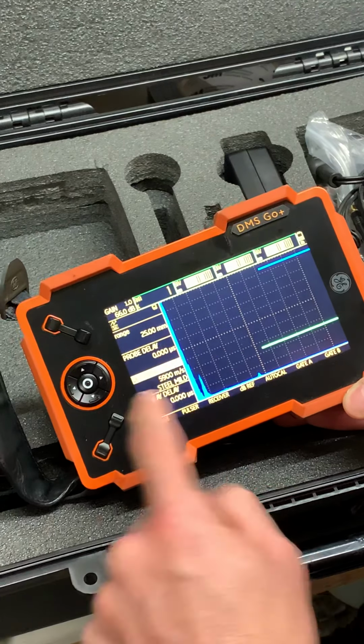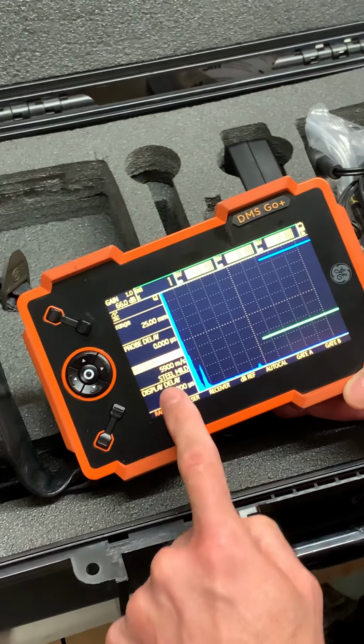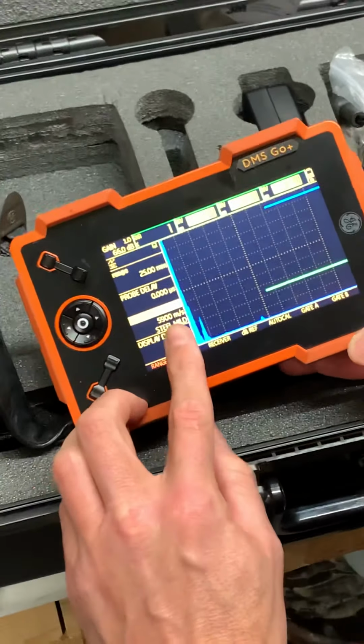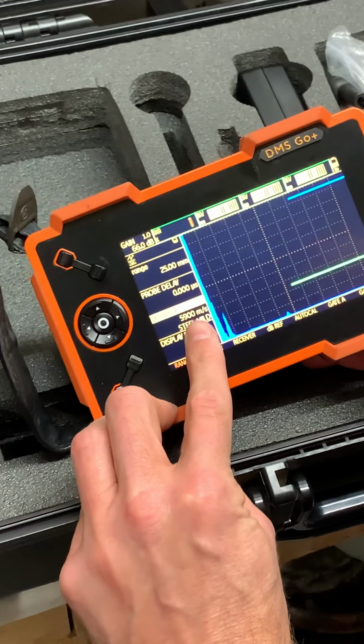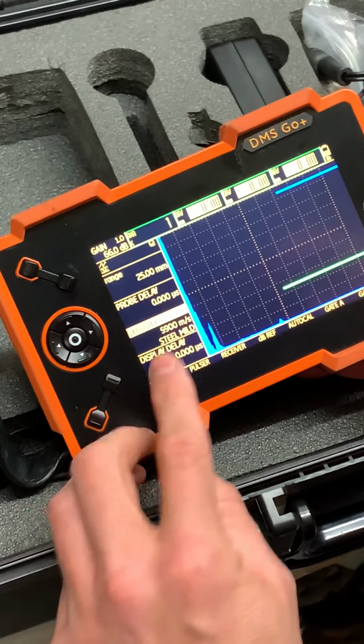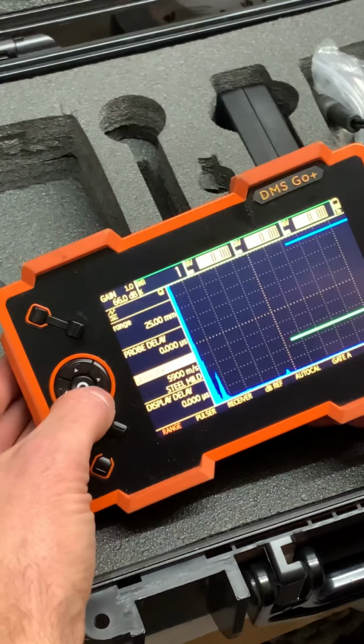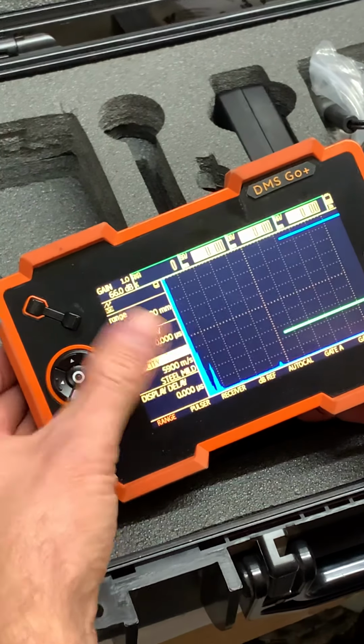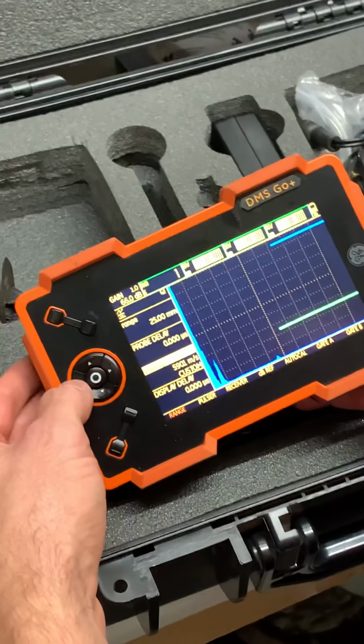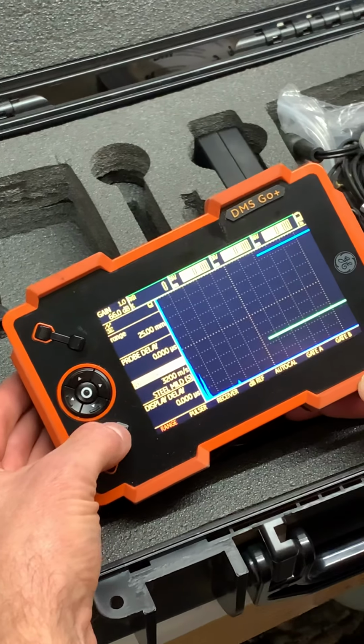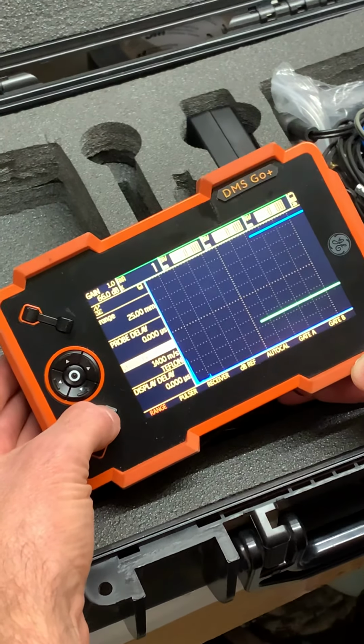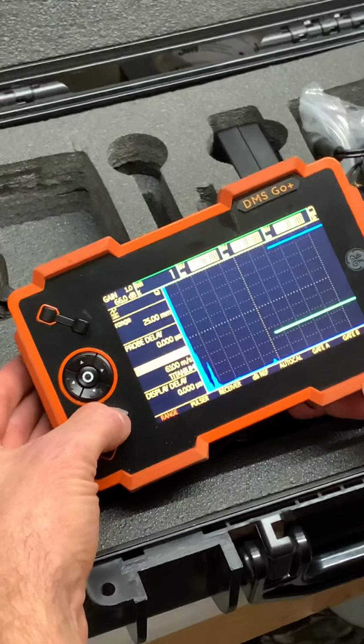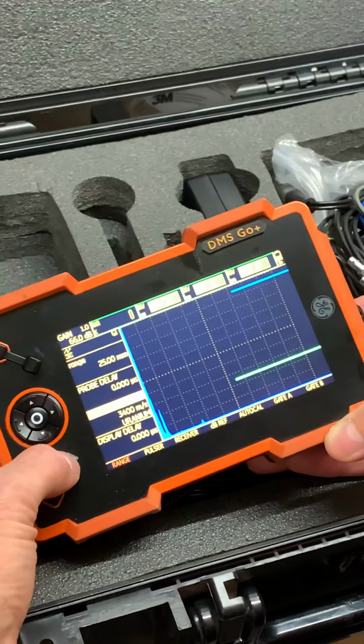Coming down to the velocity menu, it's showing the compression wave velocity for mild steel, 5.9. If I use the right button and toggle across, it goes into custom. If I use the rocker key, it goes through all the pre-programmed material velocities, just like that.